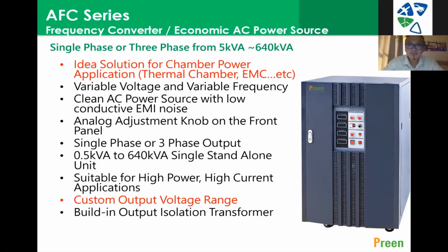You see the knobs on the front panel—this is for front panel adjustment. You can easily switch and adjust between different voltages like 208, 120. But AFC is non-programmable; if you need programmable, you have to choose the AFV product instead of AFC. AFC is usually used in production lines or laboratories where they need to change the voltage and also the frequency.